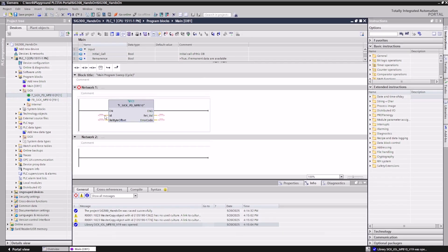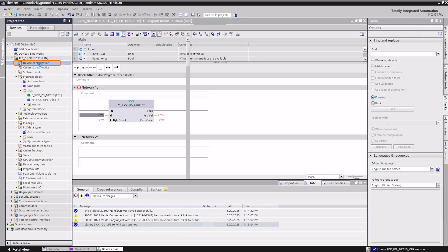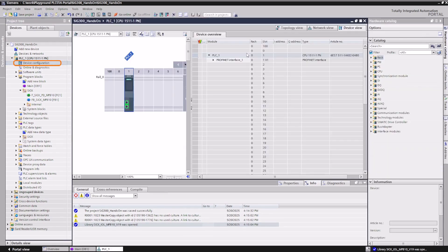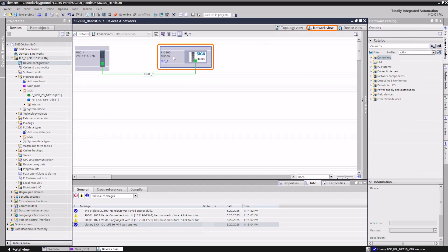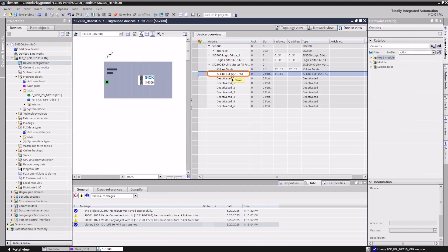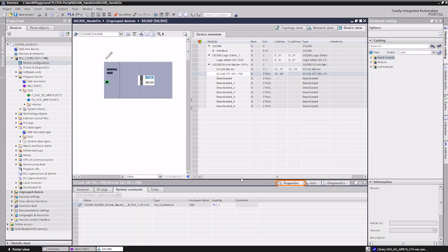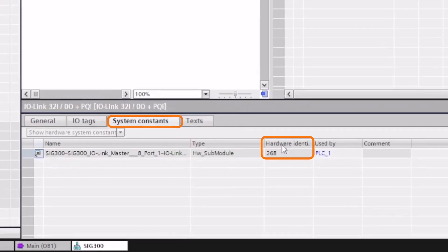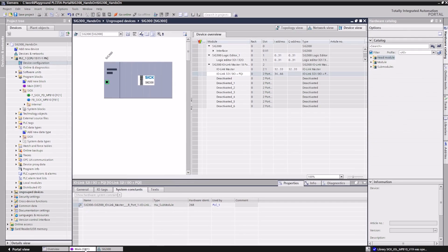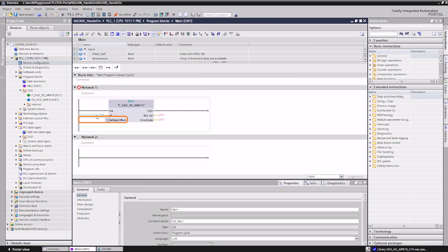We obtain the hardware identifier from the submodule, which provides the raw process data and transfer it to the ID parameter of the function. The relative byte offset is not used for the SIG 300 IO-Link master and is therefore fixed to zero.